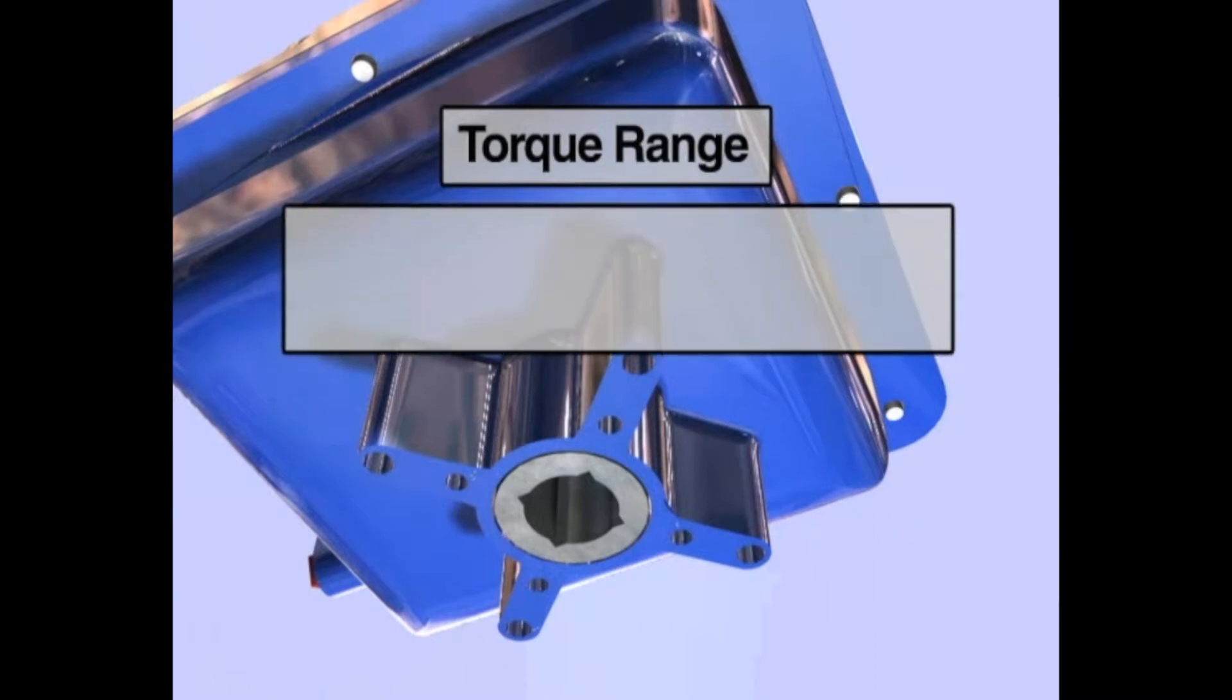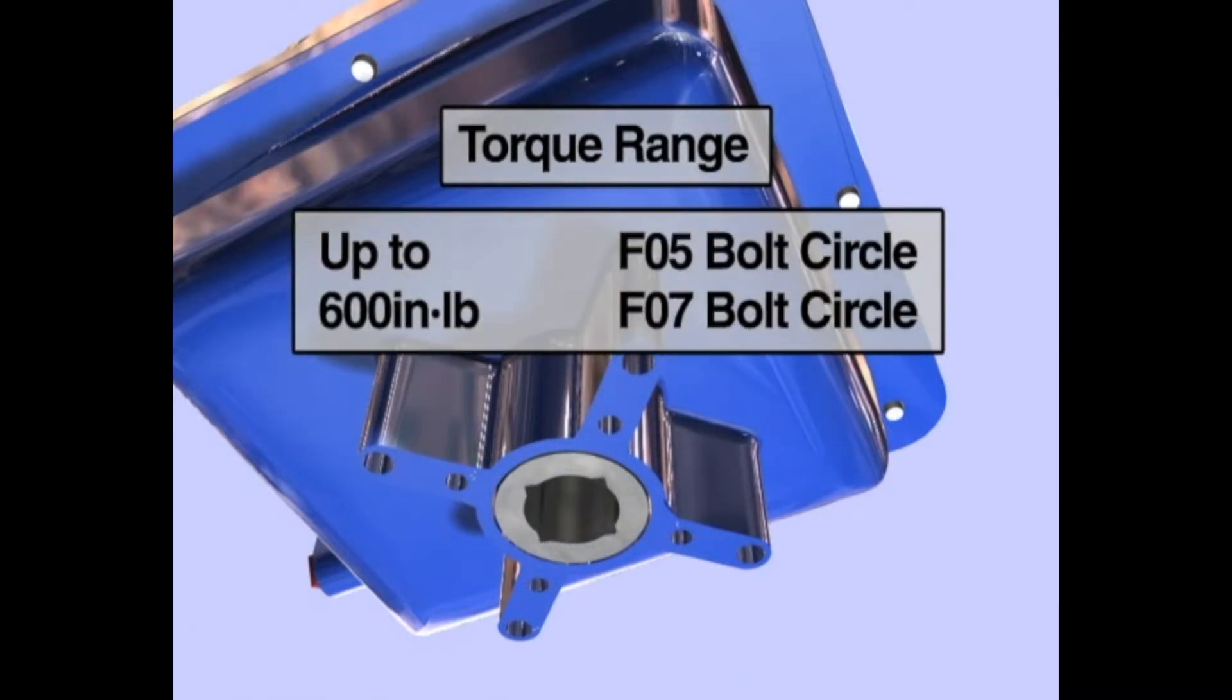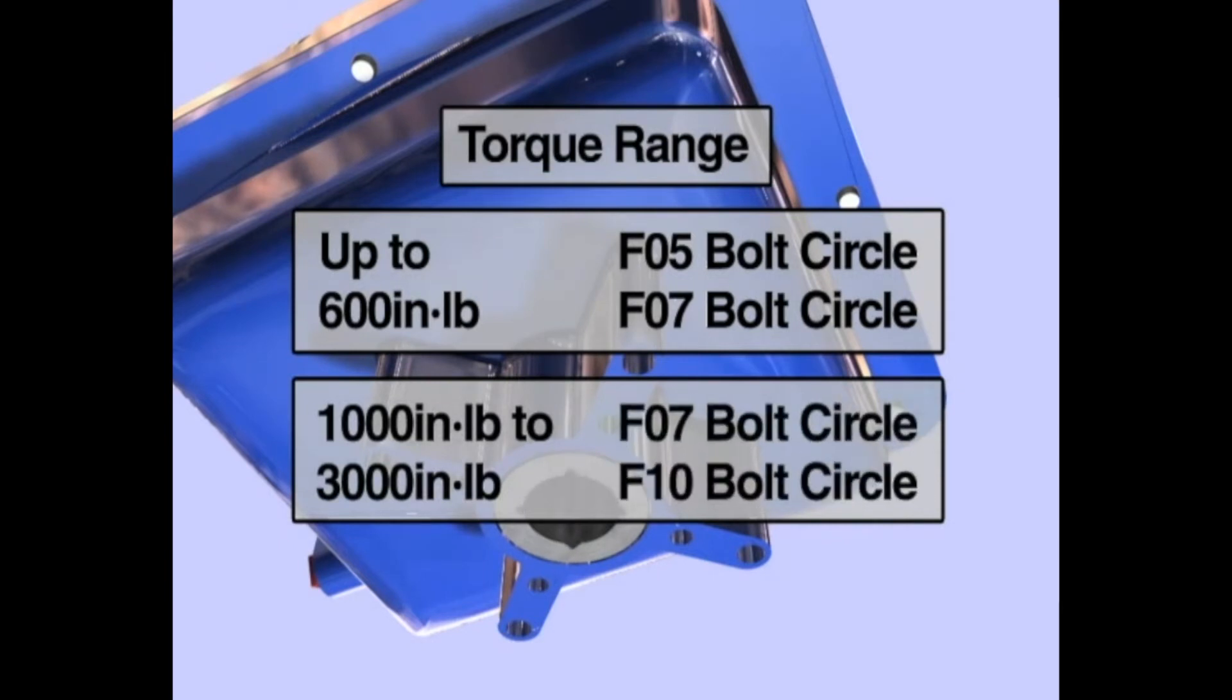For torque output up to 600 inch-pounds, the small V-Series enclosure provides F05 and F07 bolt circles. For torque output of 1,000 to 3,000 inch-pounds, the large V-Series enclosure provides F07 and F10 bolt circles. Female square output drives can be ordered in either metric or standard dimensions.